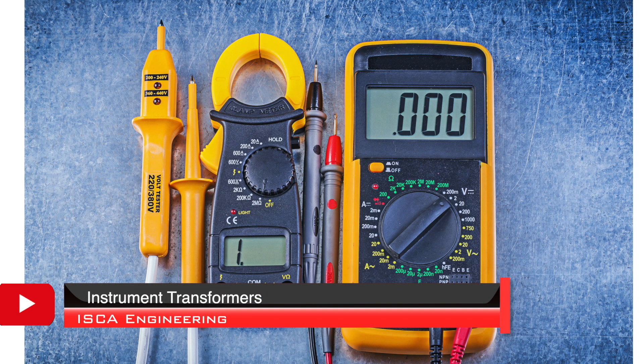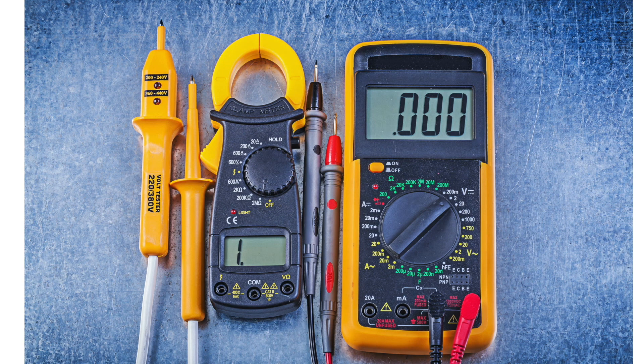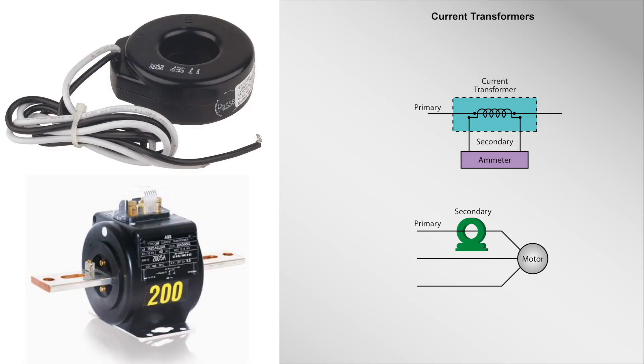Instrument transformers are used in conjunction with instruments such as ammeters, voltmeters, and relays for protective purposes. There are two types of instrument transformer, and they are the potential transformer and current transformer. The potential transformer operates in the same principle as the power transformer, except the capacity of the potential transformer is smaller. These transformers step down voltage to a lower level to make it possible to be measured by standard instruments with coil ratings of 120 volts. Current transformers are used to step down current of power systems to a lower level to make it possible to be measured by standard instruments.